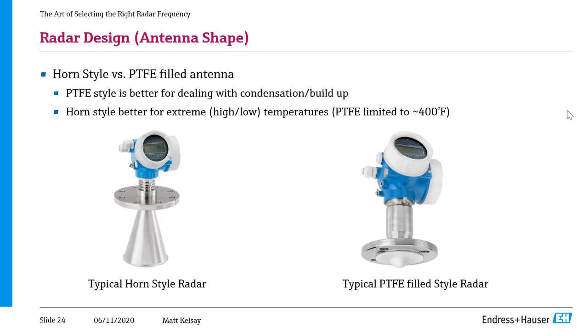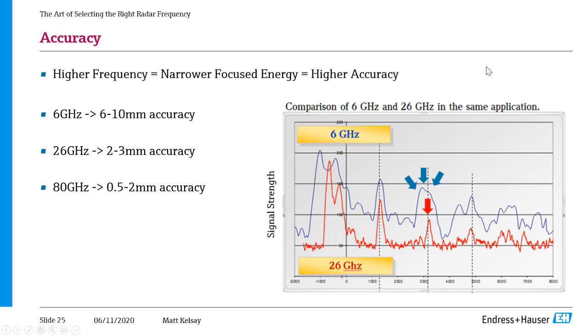Okay, next. So accuracy is also affected or influenced by the frequency range. When you increase the frequency, you're just focusing all of that energy into a more narrow band, which allows us to achieve higher accuracy. Looking at this chart on the right, let's first focus on the blue line. This blue line is representative of what a typical signal might look like for a low frequency radar device. Where those arrows are pointing is where it's saying the level is at.